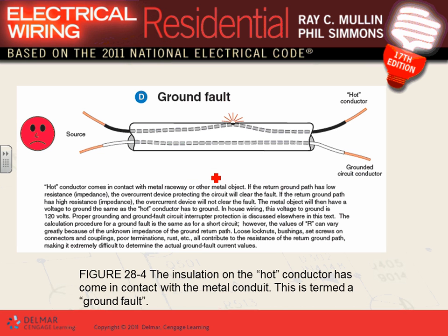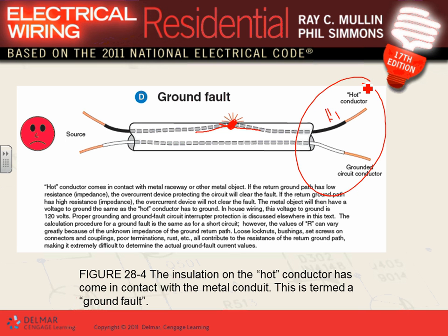Ground fault: you're pulling conductors in a conduit and you compromise the integrity of your insulation. Your hot conductor is now touching the conduit — that's a ground fault condition. The ground fault current can range from 50% of the short circuit all the way to 100%, equivalent to the short circuit, but it's typically a little lower depending on the impedance of the conduit and the contact point.